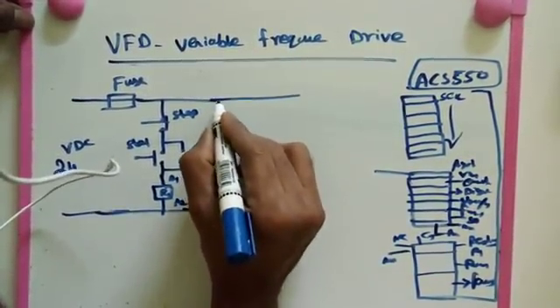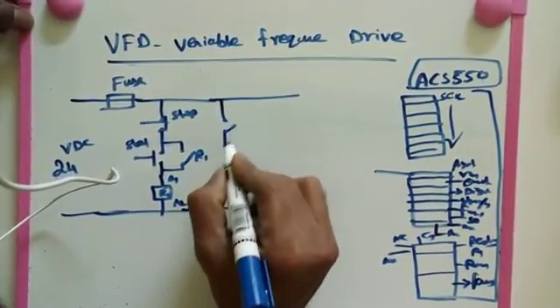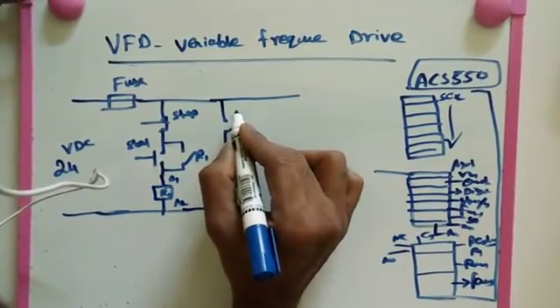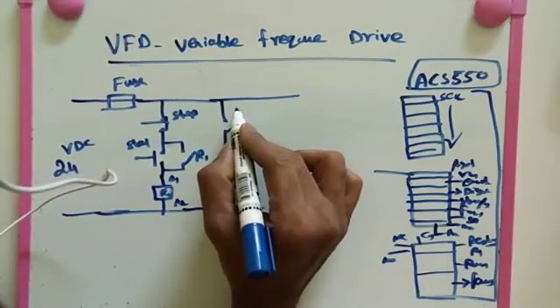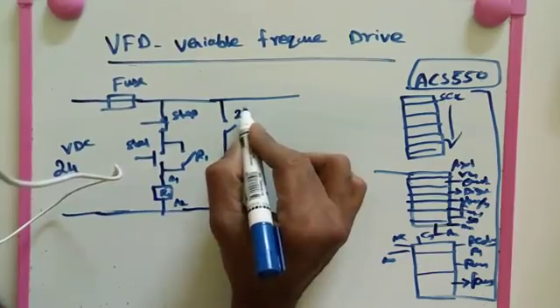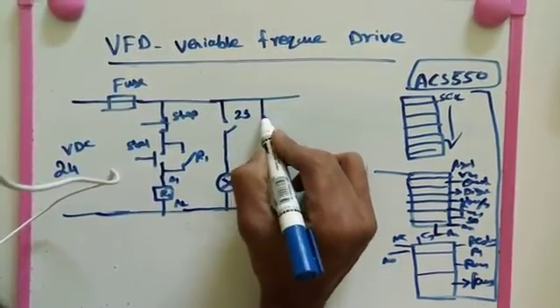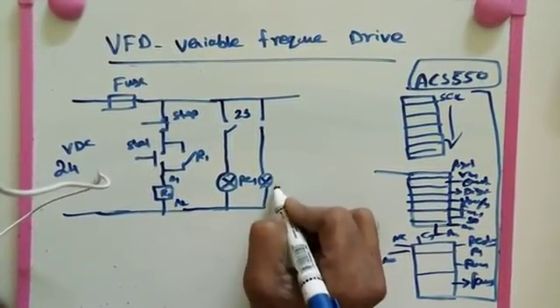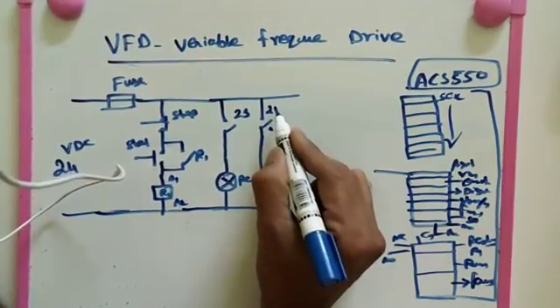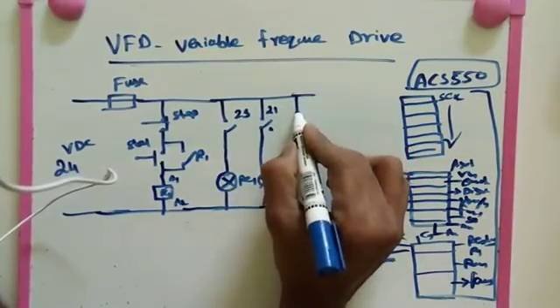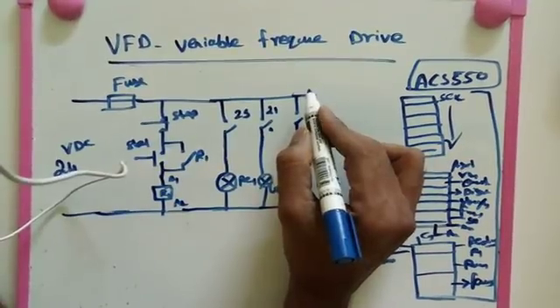After that, we add indication lamps. For run indication, we use a red lamp connected to terminal 23 on the VFD. For ready indication, we use a green lamp connected to terminal 21. For fault indication, we use a yellow lamp connected to terminal 27 on the VFD. These give us the first set of indications along with the start-stop command.